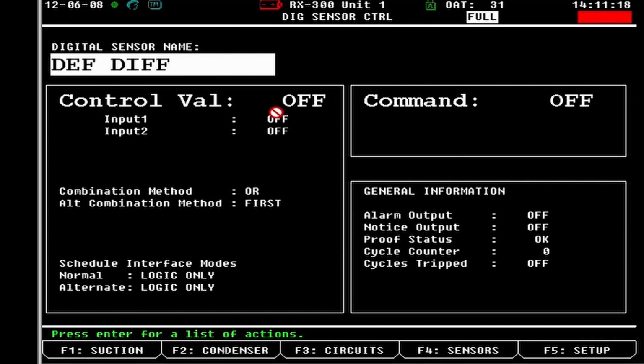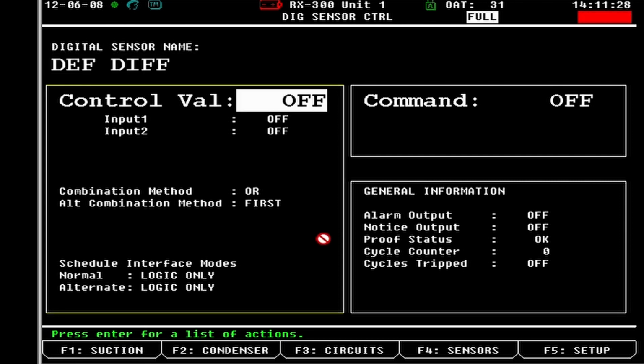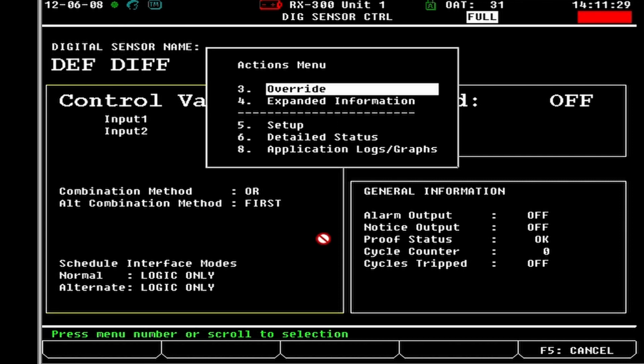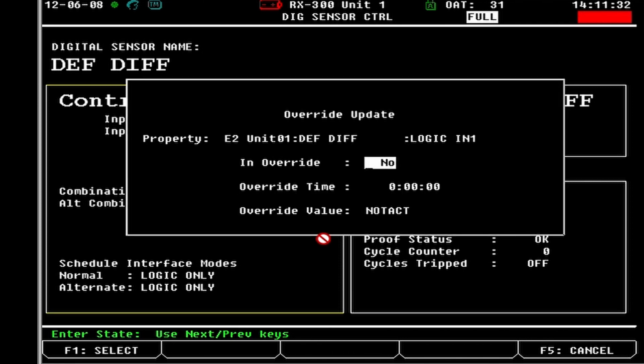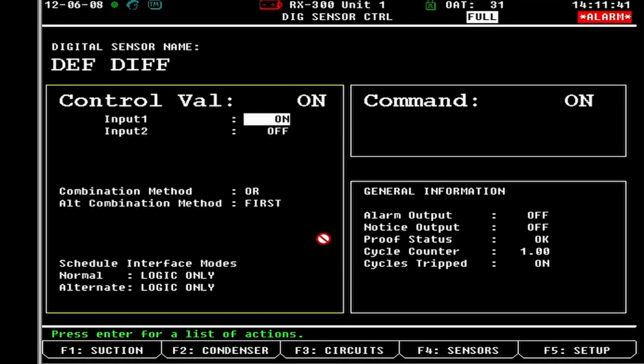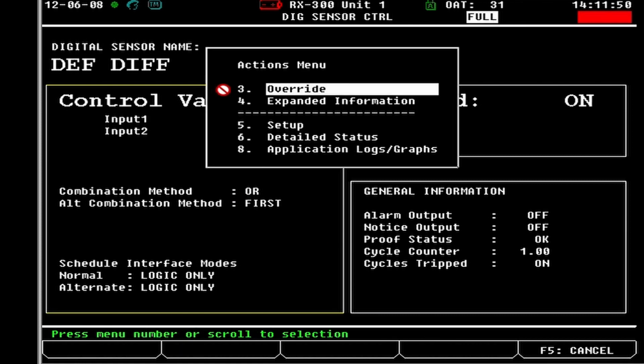So if we go to the first value and I click it, I gotta go down, I'm not on ultrasite. So if I hit enter, I go to override and I go yes, and I go on. See how input 1 is on, input 2 is off. Now it's on. So if we go likewise, we go down here, we override this to on.